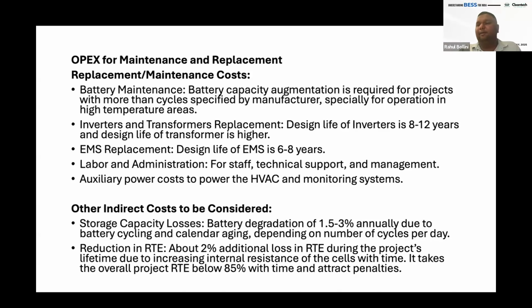And there's battery degradation, like I was saying. Indian projects typically follow 2.5% annual degradation, although batteries don't actually work like that — they degrade very high in the first 2 years and then it flattens out. To cover that initial high degradation period, we oversize the battery. We also oversize it to maintain less than 100% DOD, and to cover the losses between the battery and the measuring point. We'll come to the losses in a minute.